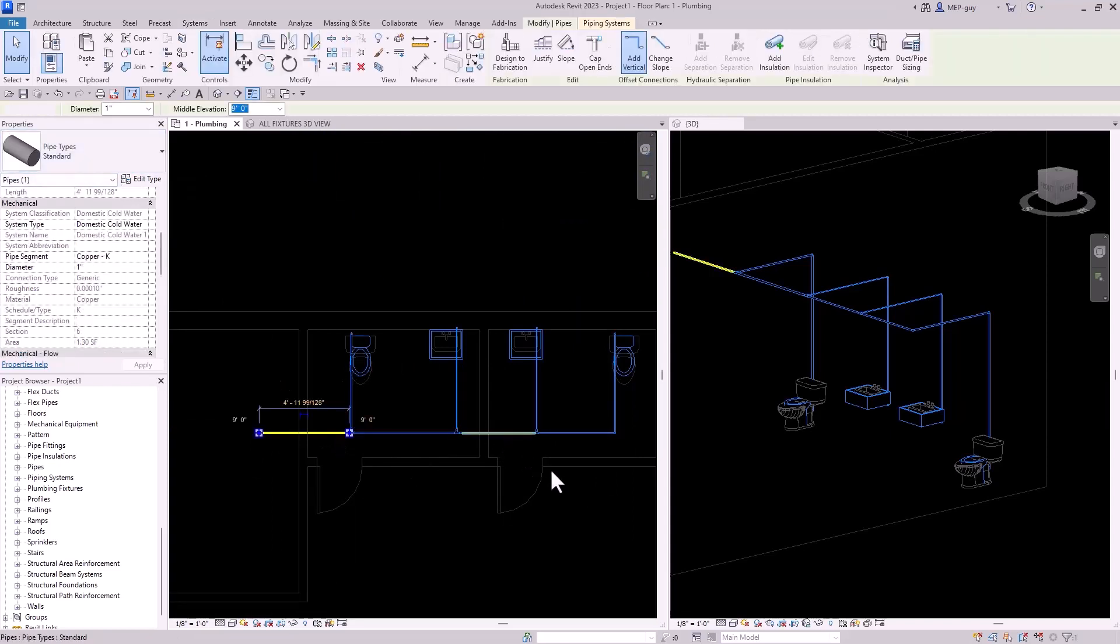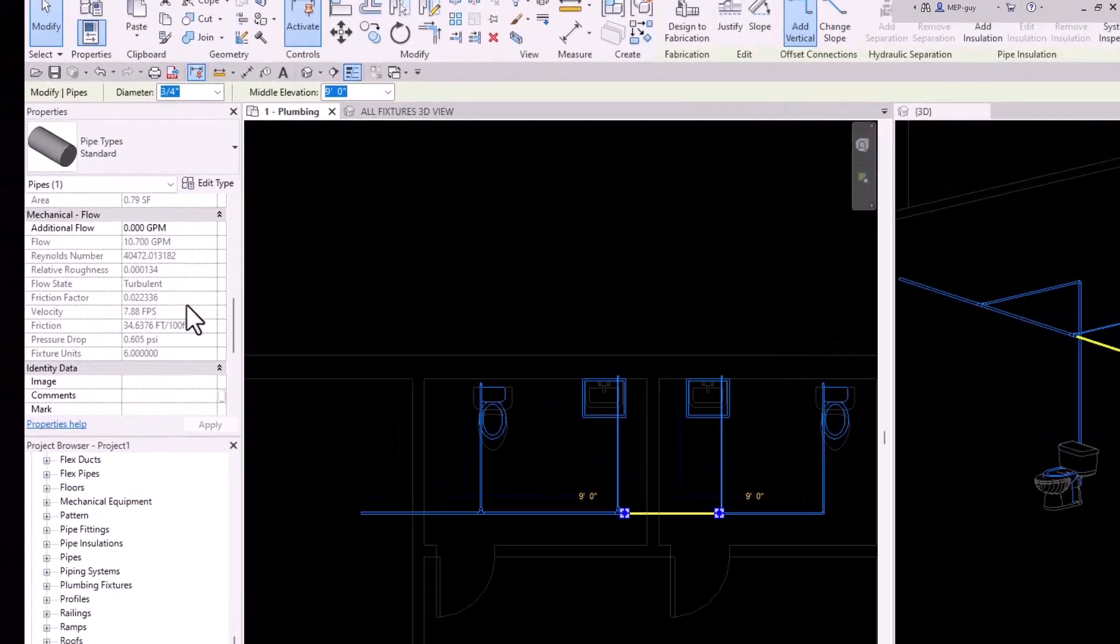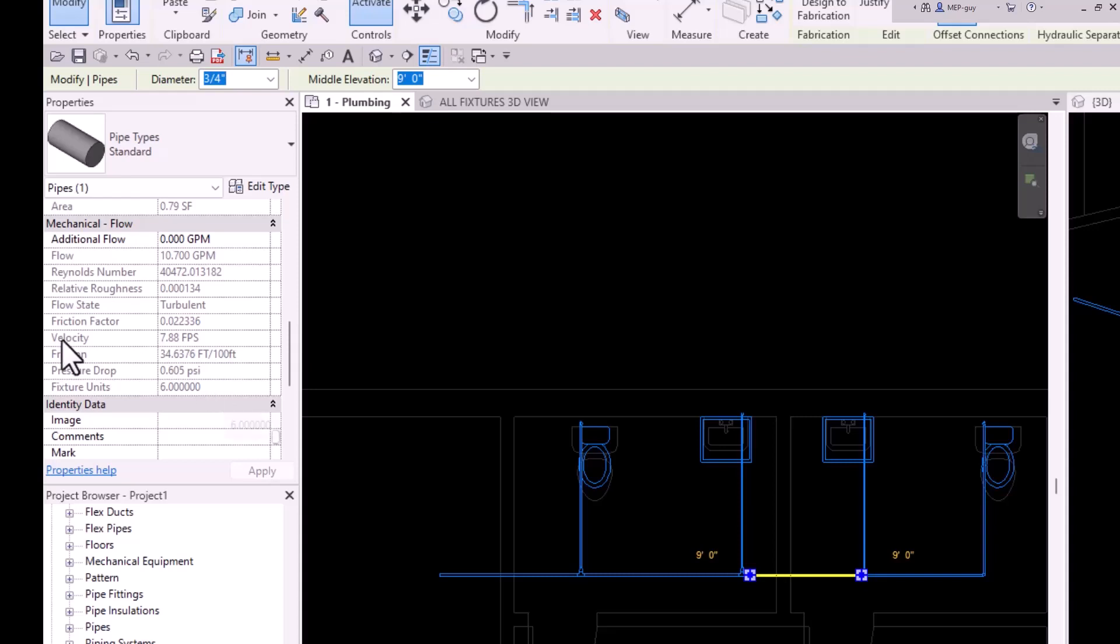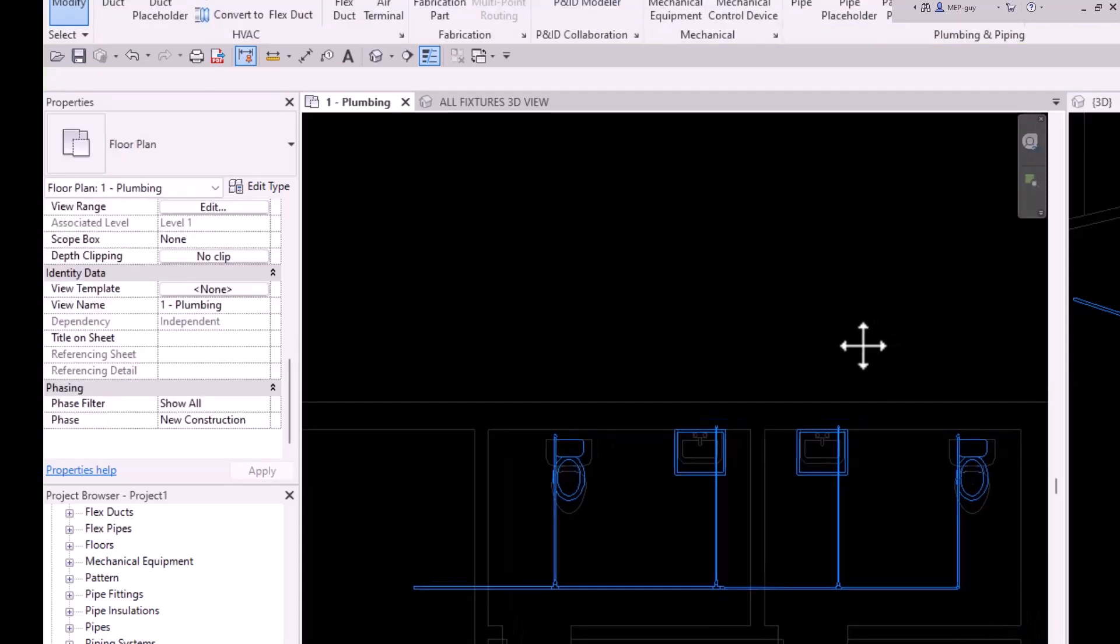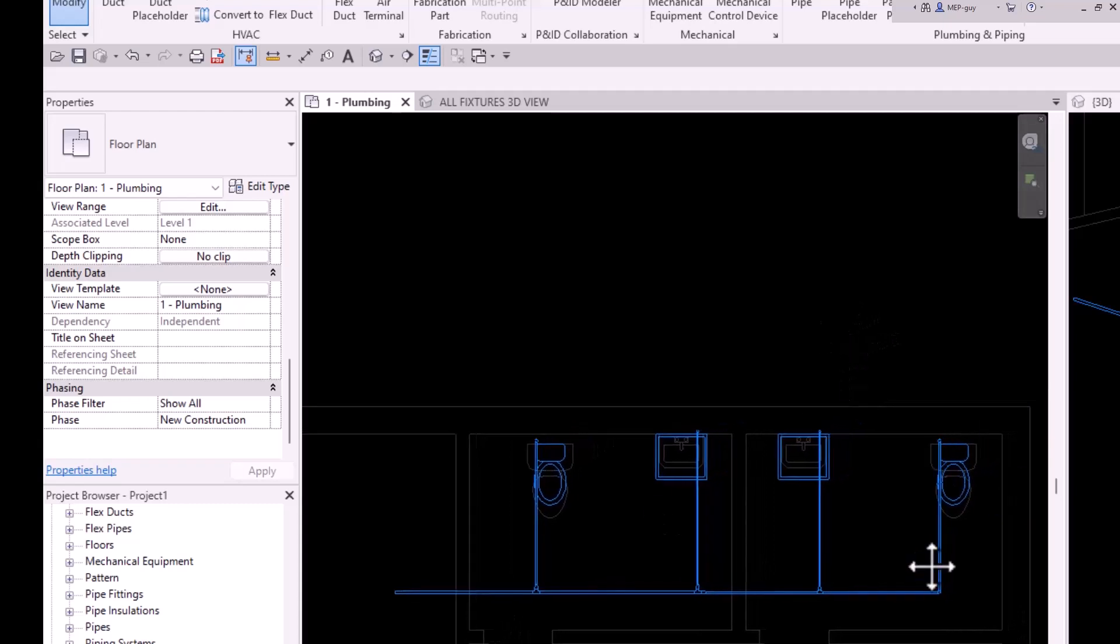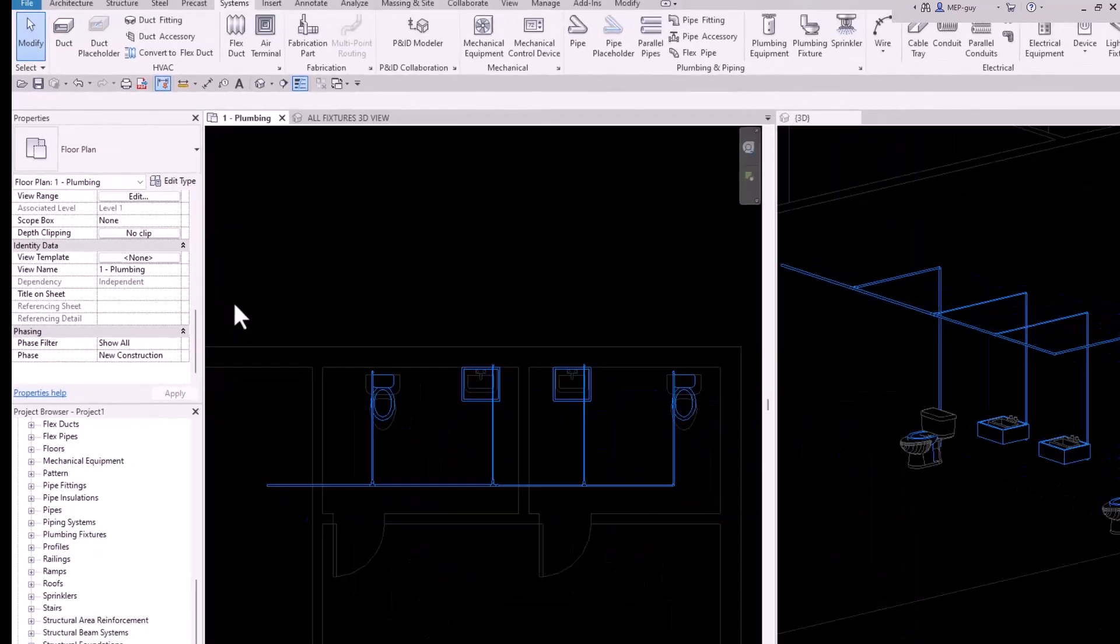So if we check on the velocities now, we still have one inch here, but then right here, it's dropped it to three quarter inch. And you can see that's because we have a lower flow in this piece of piping, only six fixture units. And the velocity is 7.88, which is less than eight feet per second. So you can see there's such a huge advantage of actually using building information modeling within your own Revit models.